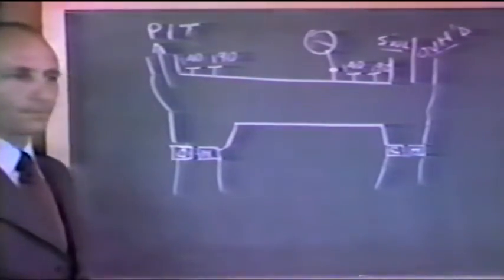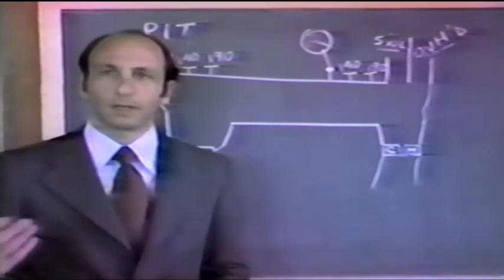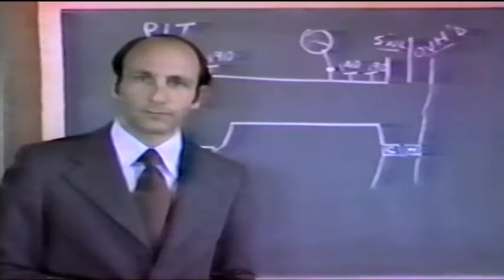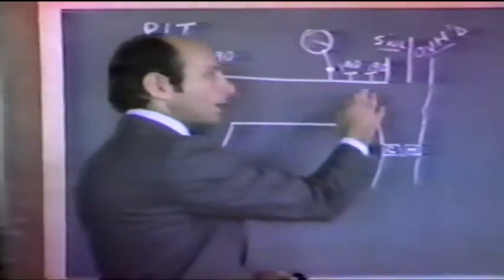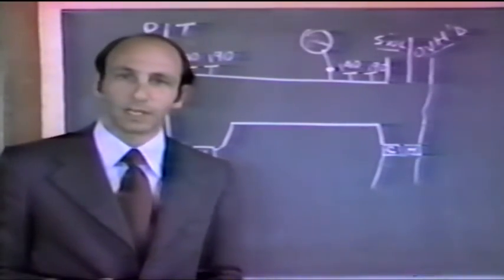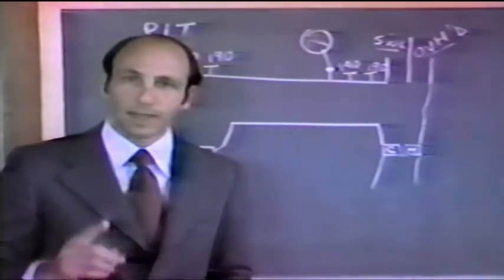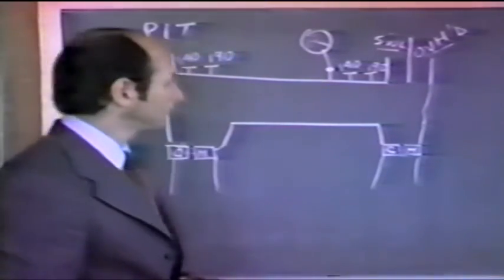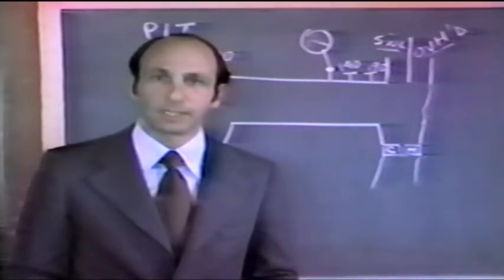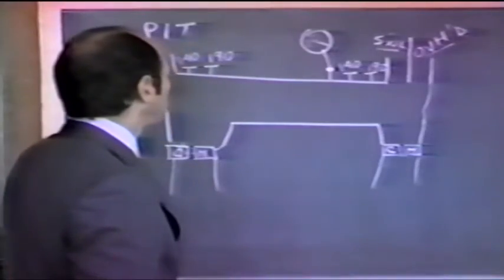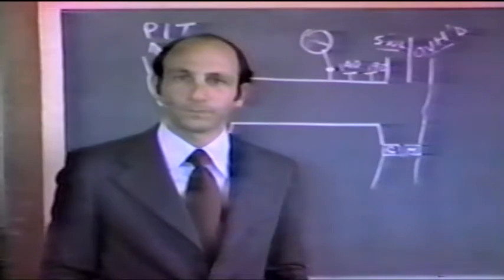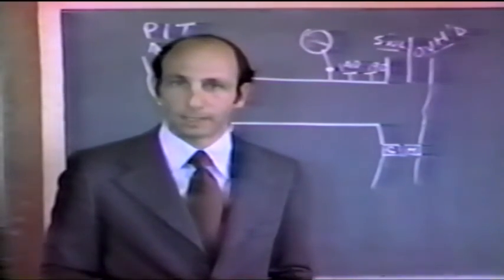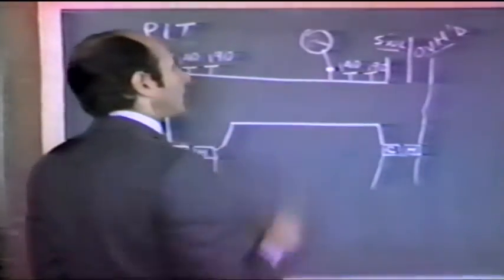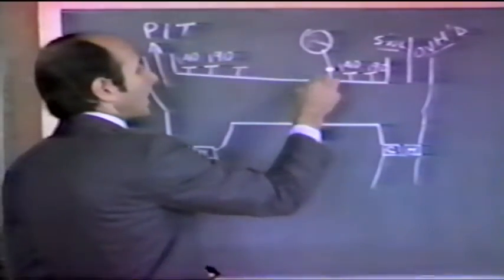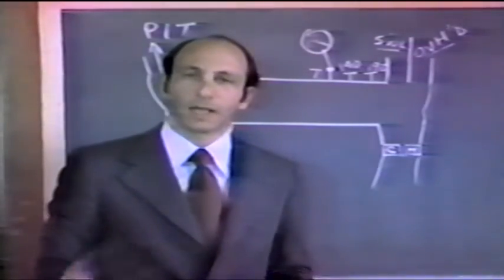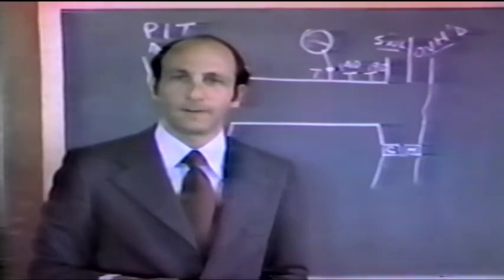What is the 140? Well, the 140 is what we call the topping circuit. If the duct temperature exceeds 140 degrees, even though we can only read that duct temperature on this side, on either side, if we are in the automatic position, then the air mix valve will not move any further toward hot. It doesn't make the air mix valve move toward cold. It just means the air mix valve will not move any further toward hot. When we reach 190 degrees on either side, then we get the duct overheat light illuminated. Okay? 190 degrees will illuminate the duct overheat light. And then if we reach off scale high, I'll call it 250 plus or minus something, off scale high on the duct temperature gauge, and it's about 250 degrees, the pack will trip.